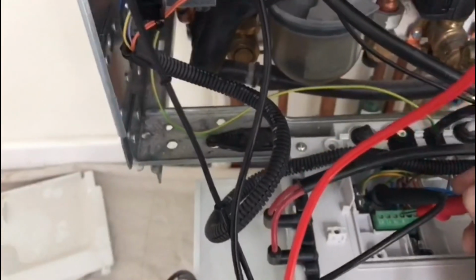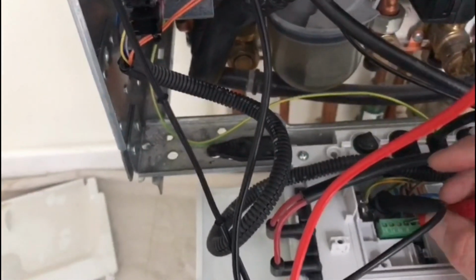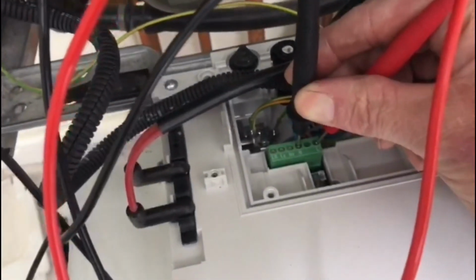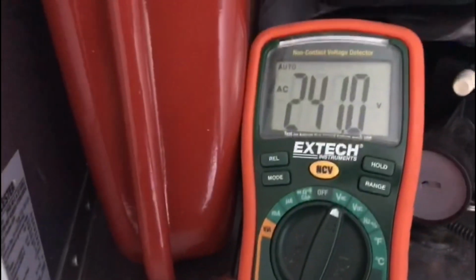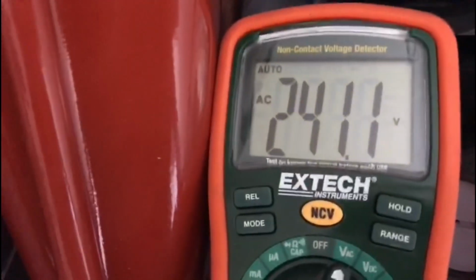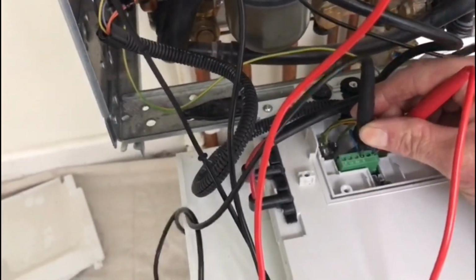Your last test is you test between the neutral and live. So I'll test between neutral and live. Excuse me while I just put my probes on. Neutral and live on the boiler, should be getting 230 volts AC, which is correct. So that tells me that my live polarity test is correct.